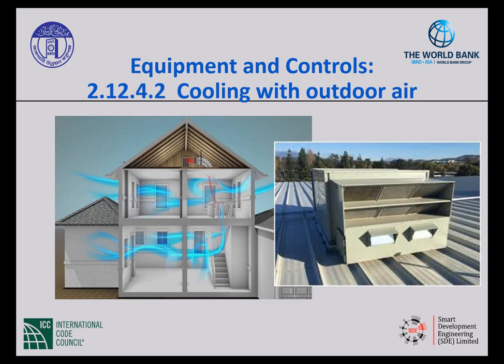maybe I'm using an air conditioner to cool a building to 75 degrees. But outside, the temperature has changed. And now the temperature outside is 70 degrees. Why am I paying to cool the air to 75 when the temperature outside is 70? I need to find a way. What are the controls or the methods that I can use to shut down this refrigeration system, or whatever it is I'm using to cool, that's using a lot of energy? It takes a lot of energy to cool a building. What can I do to shut that down and bring in the outside air? Use that outdoor air to cool the building.